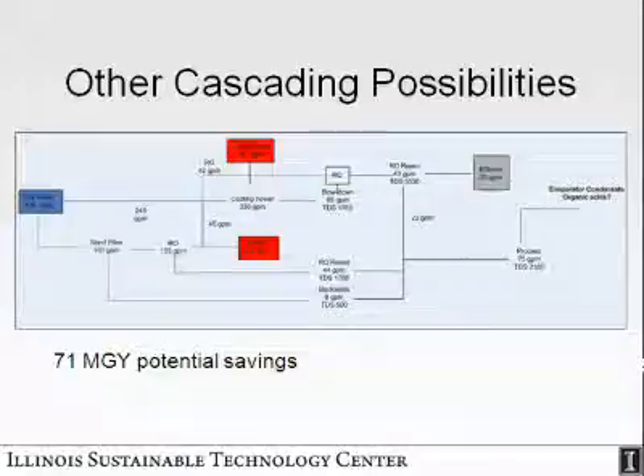If I combine a portion of that reject water with the RO reject and backwash, which have much lower levels of TDS, I can produce a combined stream that's still pretty good for process purposes. So now I've combined three different wastewater streams and substituted it for the process water. If I rearrange it this way, I can save about 71 million gallons per year compared to our baseline of 306 million gallons per year.